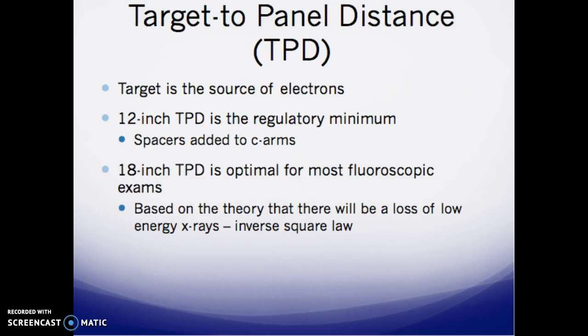Target-to-table distance (TPD): the target is the electron source within the tube. A minimum of 12 inches of TPD is the regulatory minimum. Spacers — the clear plastic cones visible on C-arms — ensure this minimum 12-inch distance is maintained. The recommended optimal TPD is 18 inches for most fluoroscopic exams, based on the loss of low-energy x-rays according to the inverse square law.